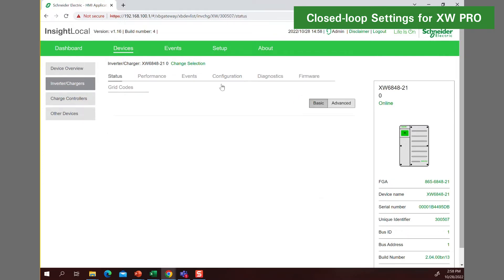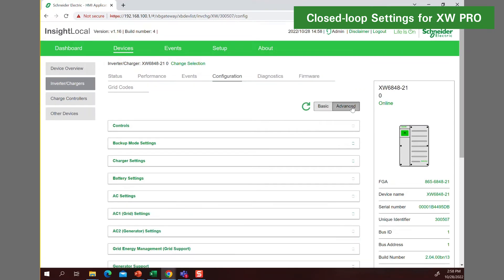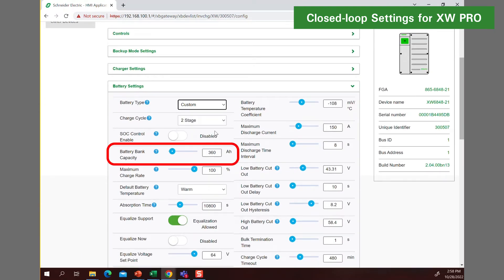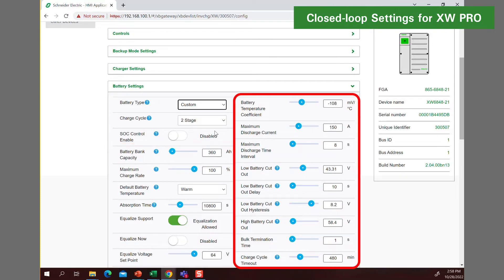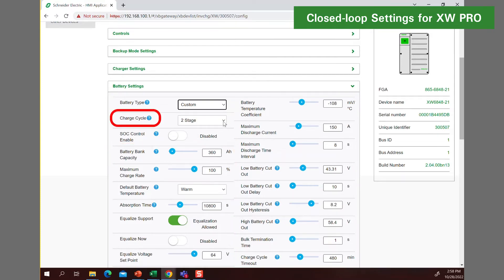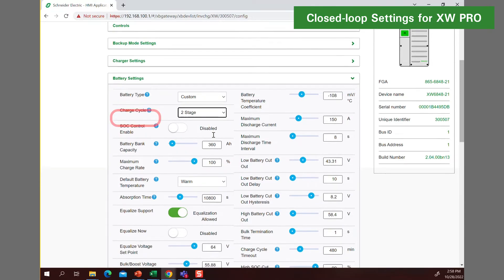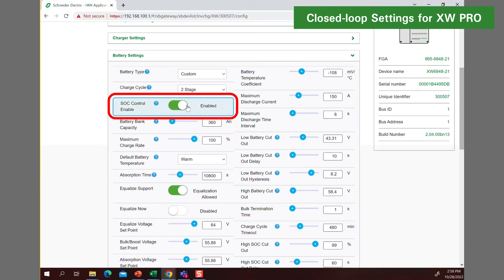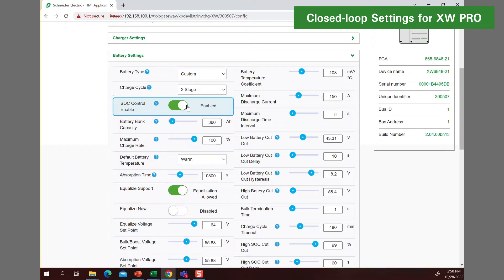Using the Insight Local web application, start by programming the battery settings. Battery type, battery capacity, and most voltage values are communicated and set by the battery. Charge cycles should be set to two-stage and the XW Pro will operate optimally if battery's state of charge control is enabled to drive inverter triggers from the SoC rather than the voltage.